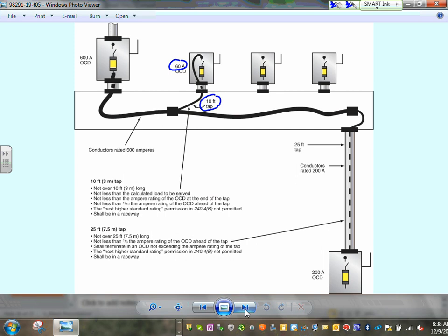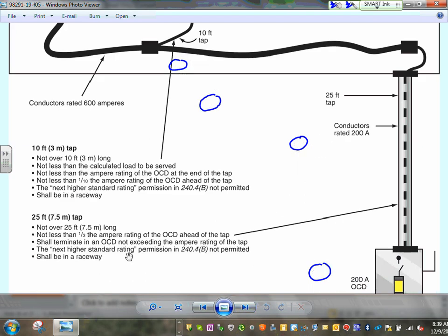And I have a 25 foot tap, and I went to a 200 amp circuit breaker. Can you guys see that? You tap the conductor. You tap the conductor. The length. So the rules for the tap are summarized right here. I'm going to go ahead and summarize the rules when you do this.